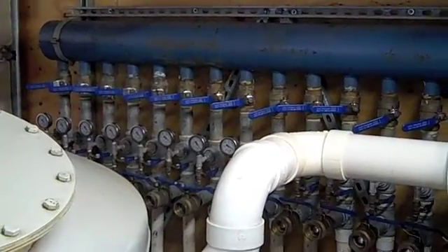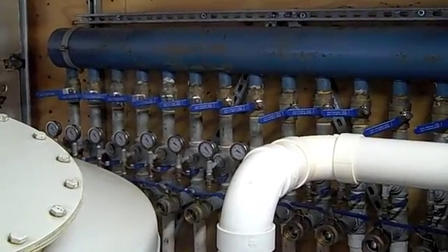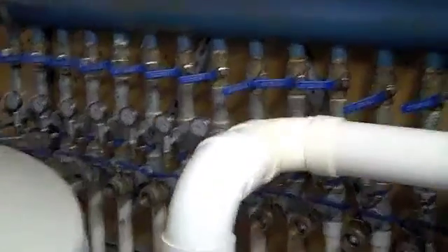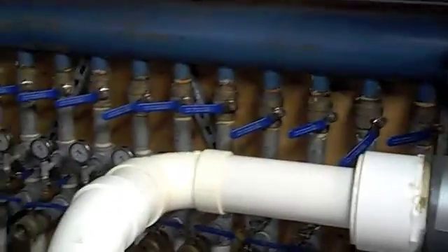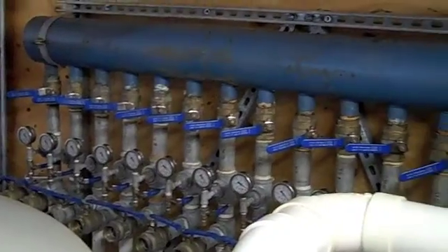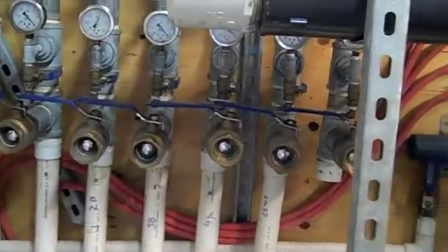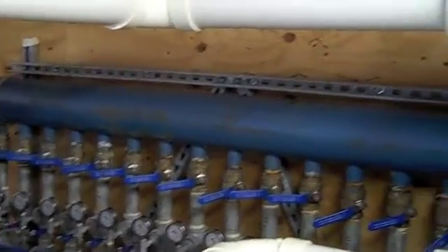This is the vapor phase of the dual phase remedial extraction system. Soil vapor extraction points run through underground trenching on individual lines coming from individual extraction points. All extraction points can be isolated inside of the remedial enclosure via ball valves. All extraction lines also include vacuum gauges to monitor extraction in individual locations. Once inside the shed, the individual extraction lines all form a common line.